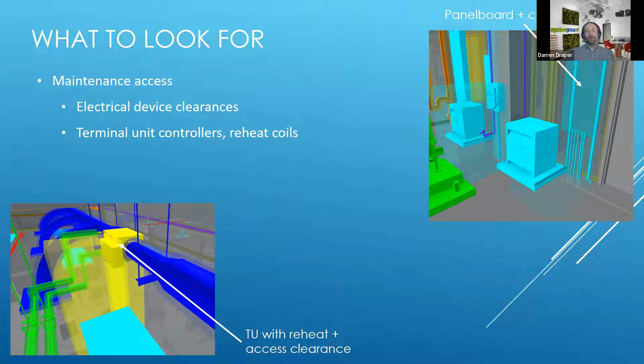Another one here on the top right is a panel board showing the maintenance clearances. That has often not been modeled from our experience - it's good to see it becoming more the norm. It's a little hard to see, but there's a maintenance clearance in very faint blue to ensure we have code required clearances. Something extremely difficult to fix after the fact is once things are installed and you take a tape measure off the face of that panel board and find a piece of pipe at 26 inches away - something has to move. We've had that happen at our firm a few times, where plumbing or mechanical pipe had to be moved to meet the code required minimum clearances.